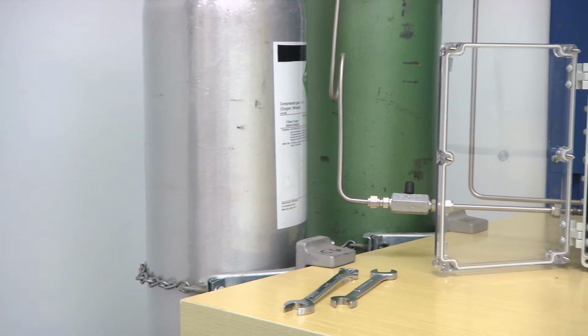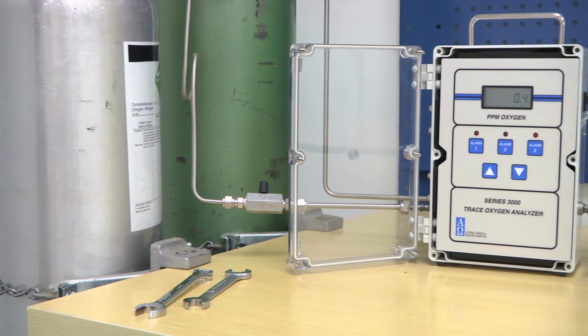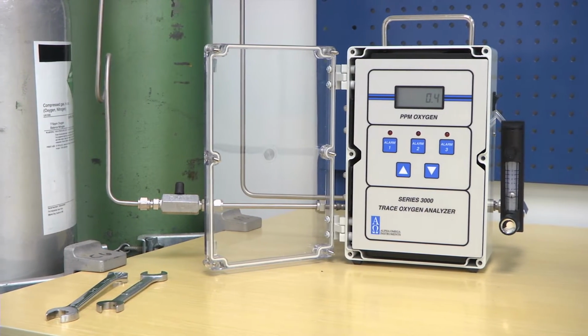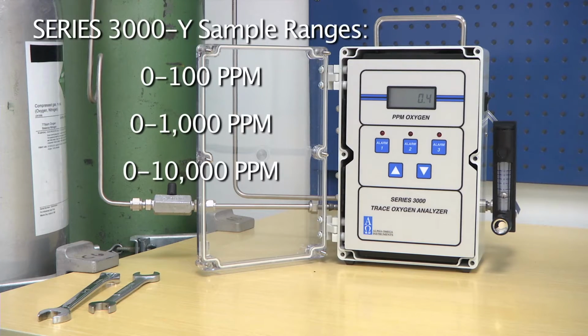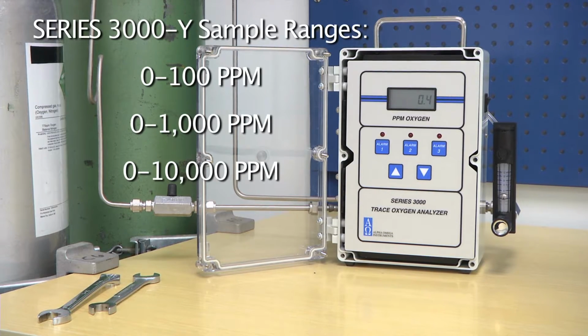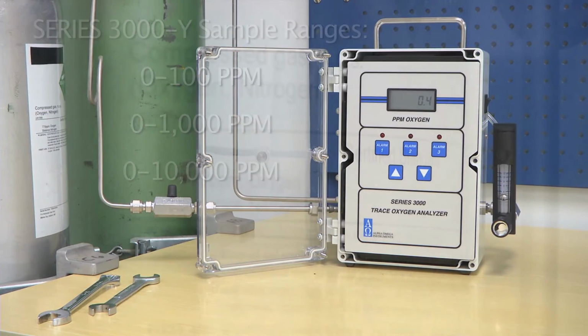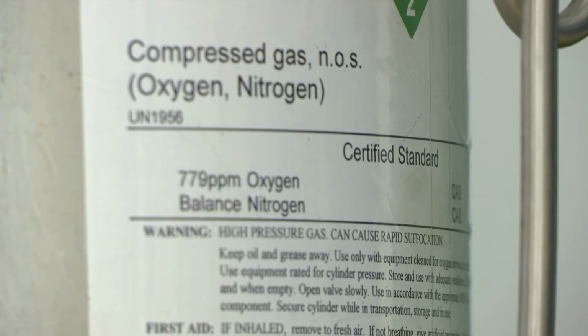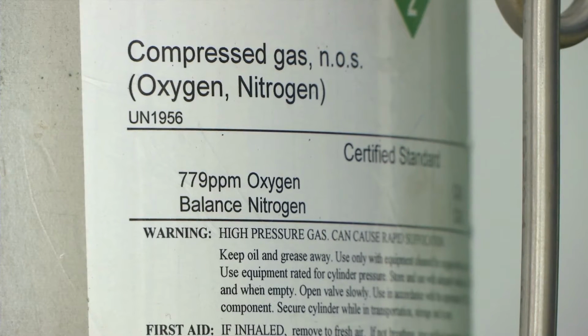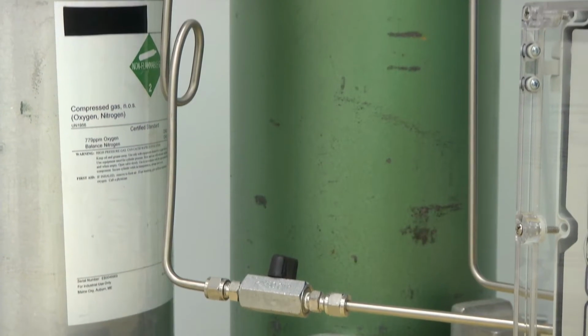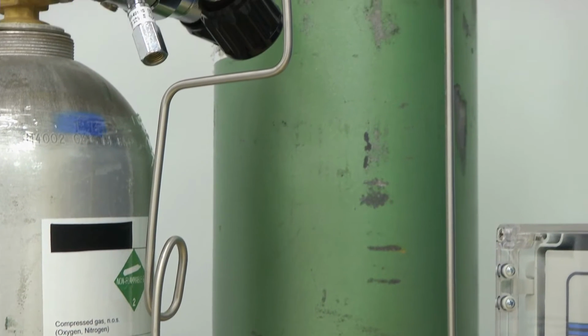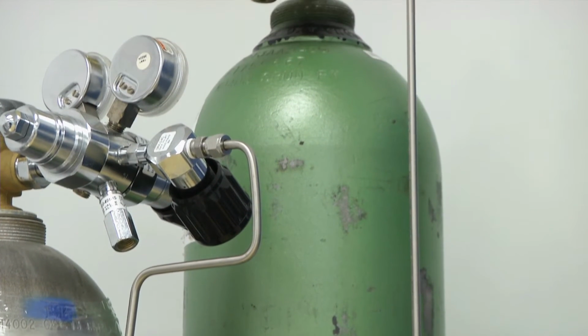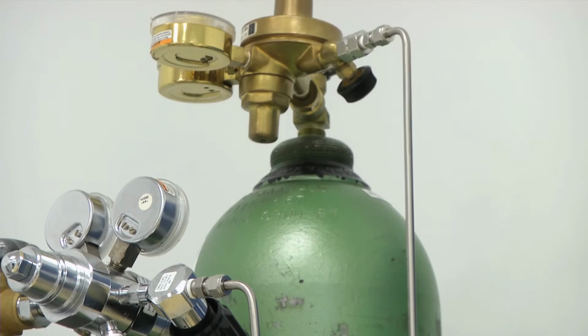The Series 3000 in this video is capable of measuring oxygen concentrations over three ranges: 0 to 100 ppm, 0 to 1000 ppm, and 0 to 10,000 ppm. Our calibration gas has been certified to have a concentration of 779 ppm of oxygen with the balance of nitrogen. Please keep in mind that the oxygen value of the calibration gas you decide upon can be different as long as it falls within the overall range of your Series 3000.